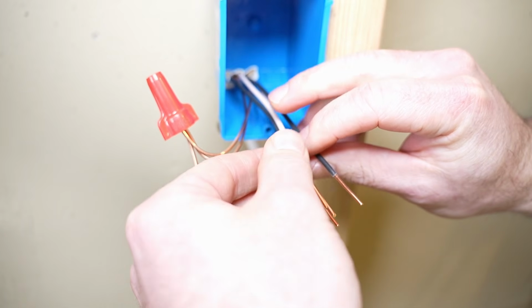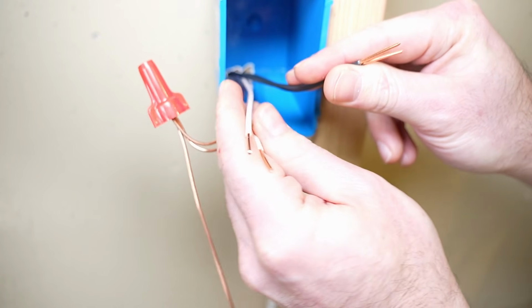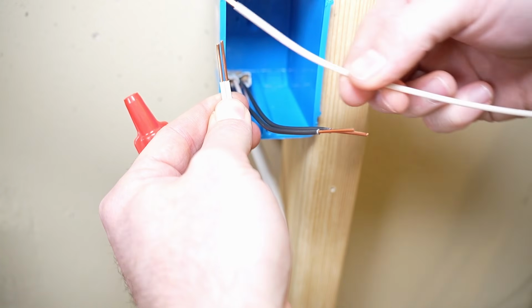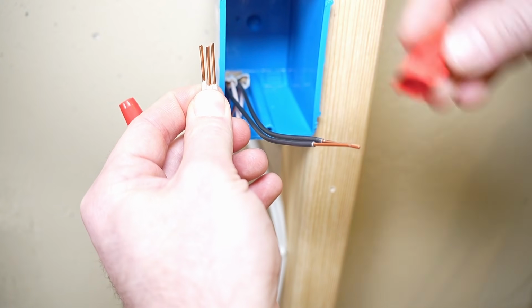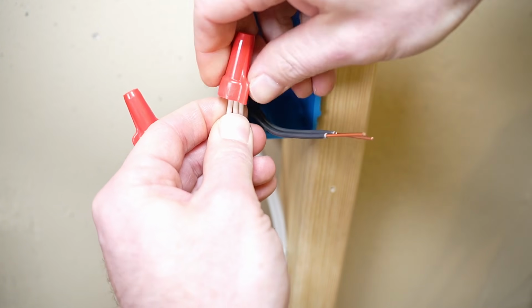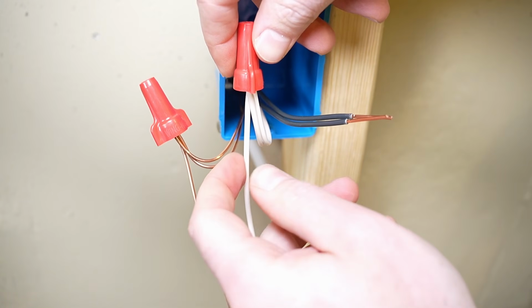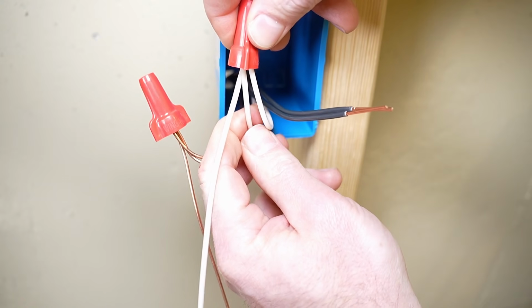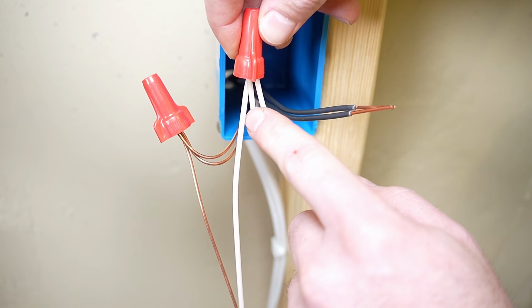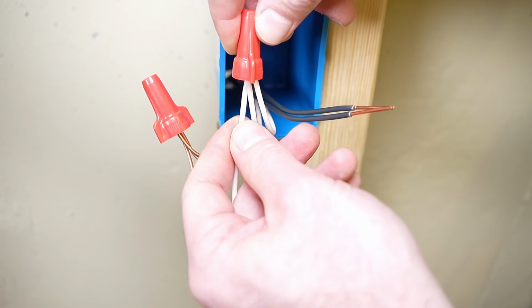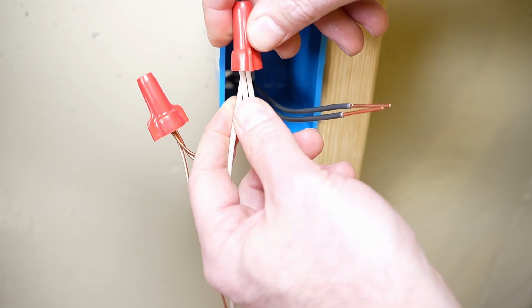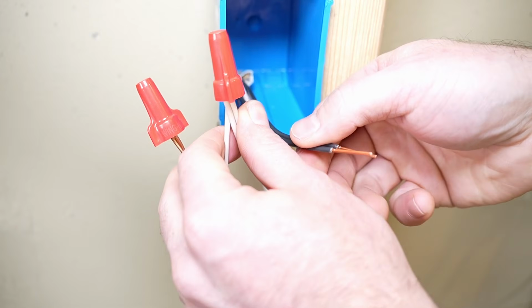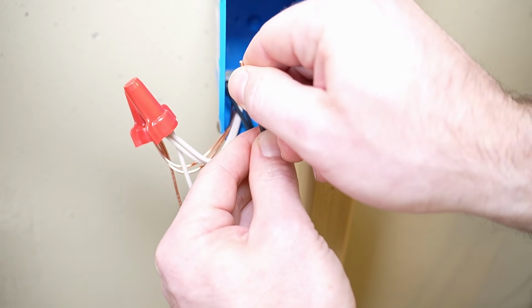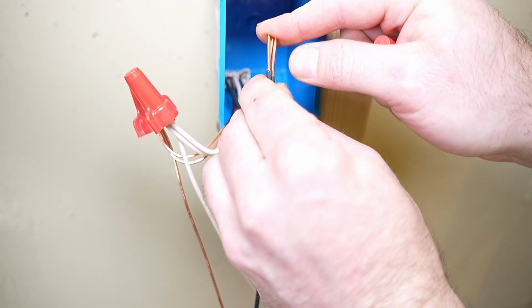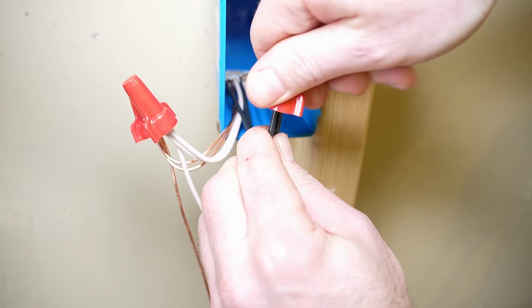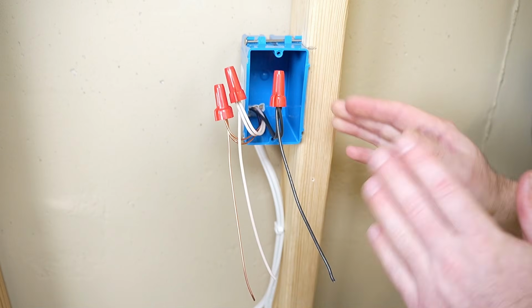Now we can move on to the next set of wires. I'm going to go with the neutrals next. Line the tips of the wires up and grab our neutral pigtail. Line all of the neutrals up and we can twist the wire nut on. Anytime we make a splice with a wire nut, we want to do a tug check. Pull on every single wire. Nothing should move. If even one of your wires moves coming out of the wire nut when you do your tug check, you have to redo the entire splice. That means it is not solidly connected. And lastly, we can do our hots here. Grab our pigtail for the hot, line everything up, and twist on our wire nut. And there we go, everything is spliced.